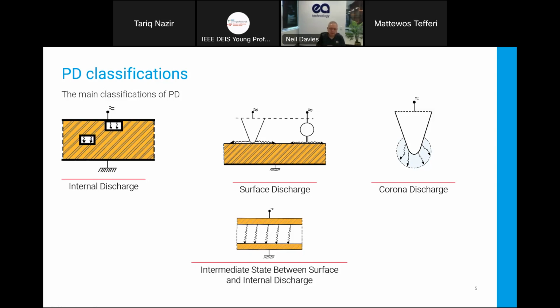Often I characterize that as one of the most dangerous types of insulation or PD classifications for switchgear in particular, because it's the sort of thing that you're never going to see, never going to smell, you're never going to hear any fizzing, crackling, you're never going to smell the ozone, nitrous oxides that are developing if it's deep inside solid insulation. So sometimes the first indication of PD, if you're not doing any testing, is that it disruptively fails.